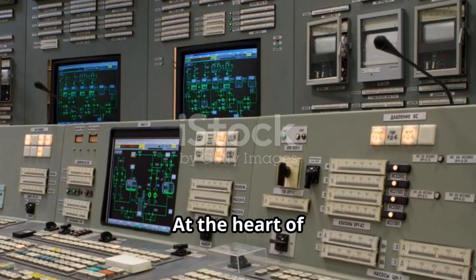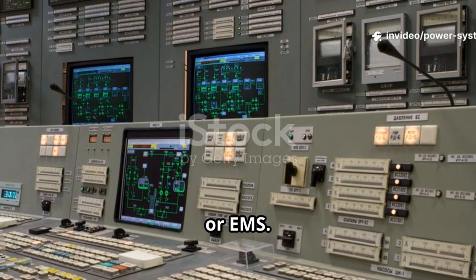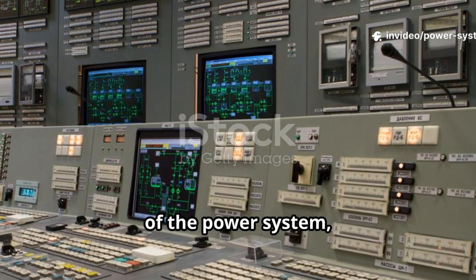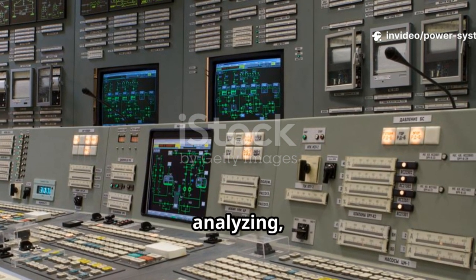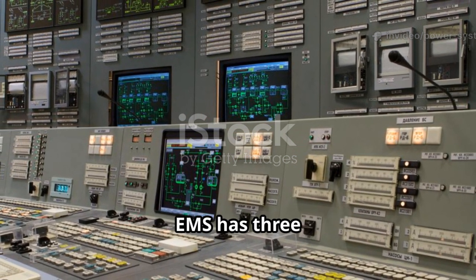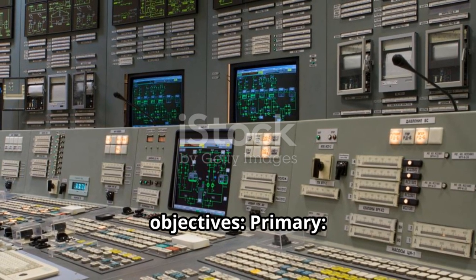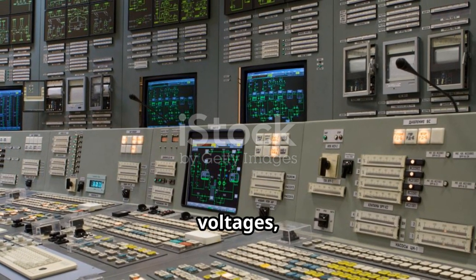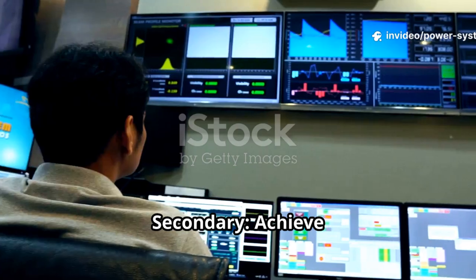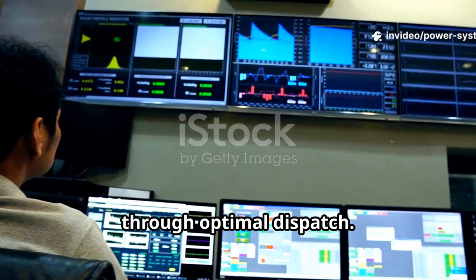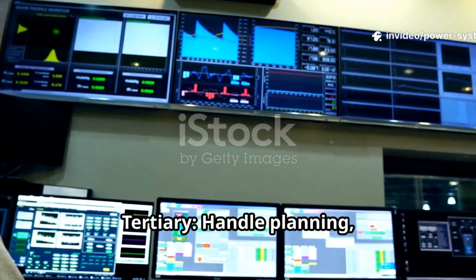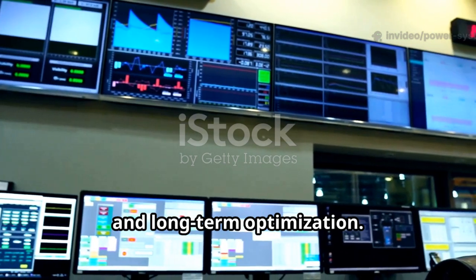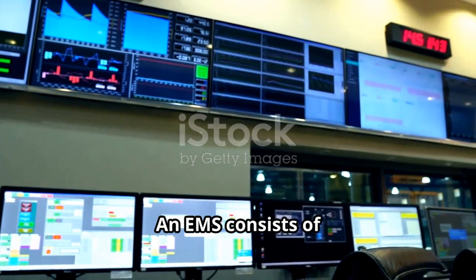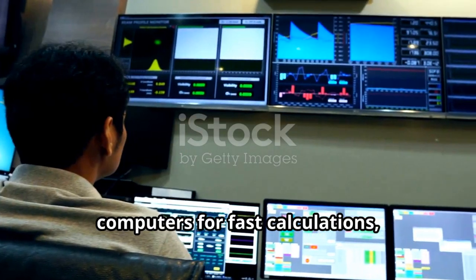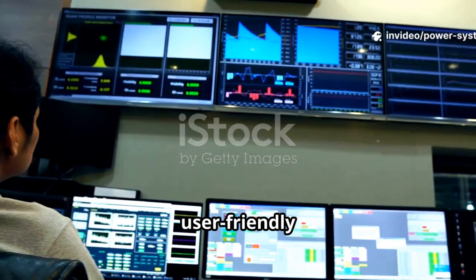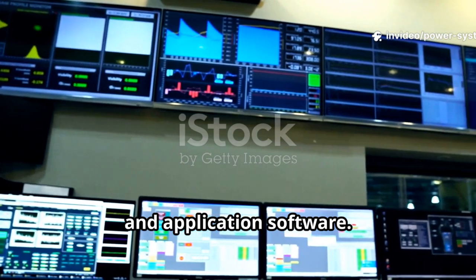At the heart of modern grids is the Energy Management System, or EMS. It's like the brain of the power system, continuously monitoring, analyzing, and optimizing operations. EMS has 3 levels of objectives. Primary, maintain frequency, voltages, and tie line power within limits. Secondary, achieve economic operation through optimal dispatch. Tertiary, handle planning, maintenance scheduling, and long-term optimization. An EMS consists of SCADA for monitoring, computers for fast calculations, user-friendly graphical interfaces, and application software.